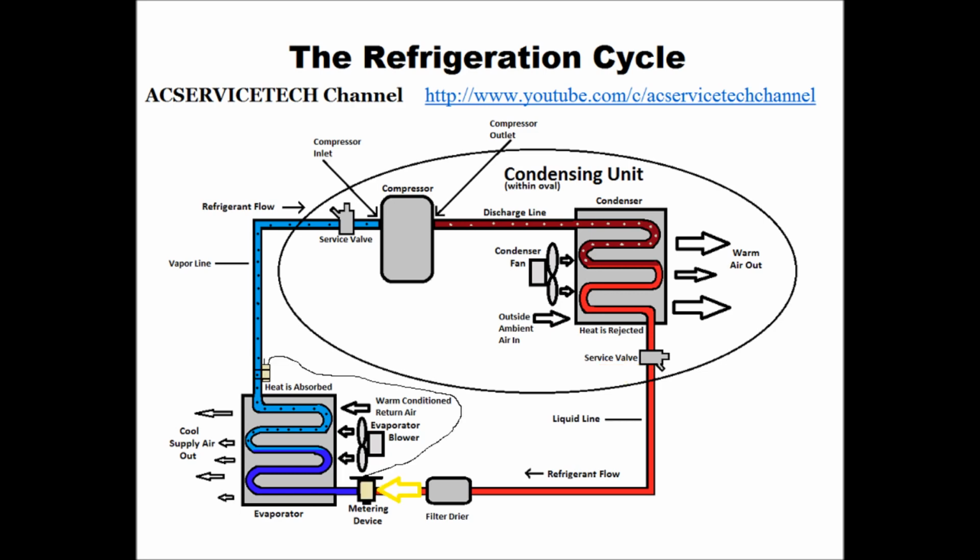All right, now superheat is very important, right? You have to have superheat. Now, a thermostatic expansion valve will actually control the superheat by itself, as long as the refrigerant charge is correct. And the superheat is a temperature increase in vapor form, and you have to have superheat, which means that you're guaranteed to have vapor going into the compressor. If you have superheat, you know you're going to have vapor going into the compressor. If your superheat is 0, or even 1 or 2, by the time it gets to the compressor, there potentially could be some liquid getting into the compressor.